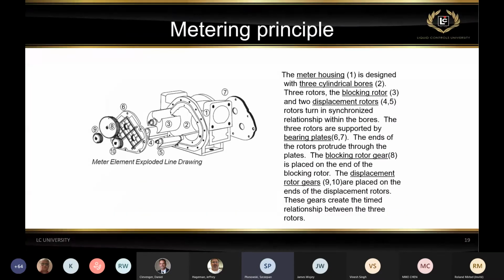So for those of you that attended the meeting about the meter principles, you remember that the LC meter is a fairly simple design. It has a basic measuring element with only nine parts. We have the housing, which is this. We have three rotors inserted into the bores of the housing, which are cylindrical bores. We have a blocking rotor, and we also have two displacement rotors.